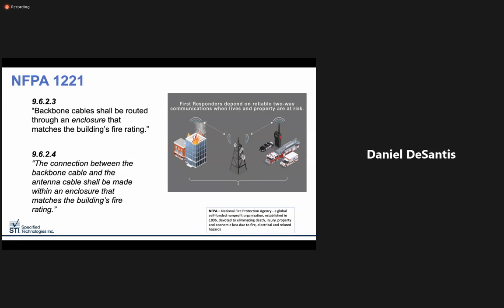NFPA 1221 is a very broad standard that covers everything from hardware coverage to coverage requirements for your in-building wireless communication systems. But what we'll be focusing on next is the rated enclosure aspect of the code. There's two specific mentions in the standard regarding rated enclosures. Both can be found in Chapter 9.